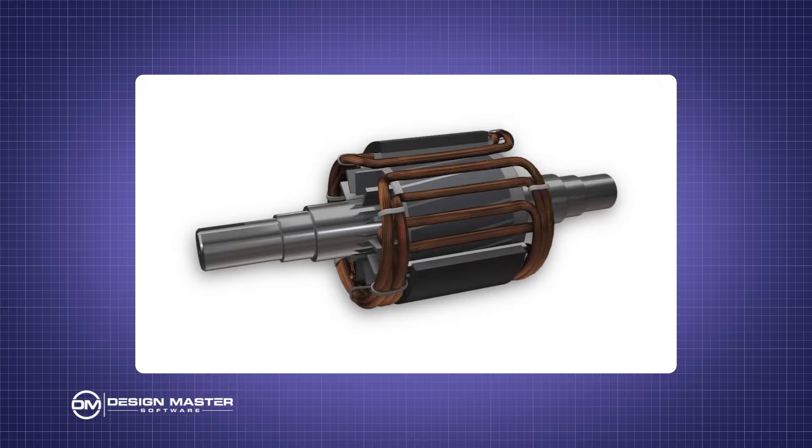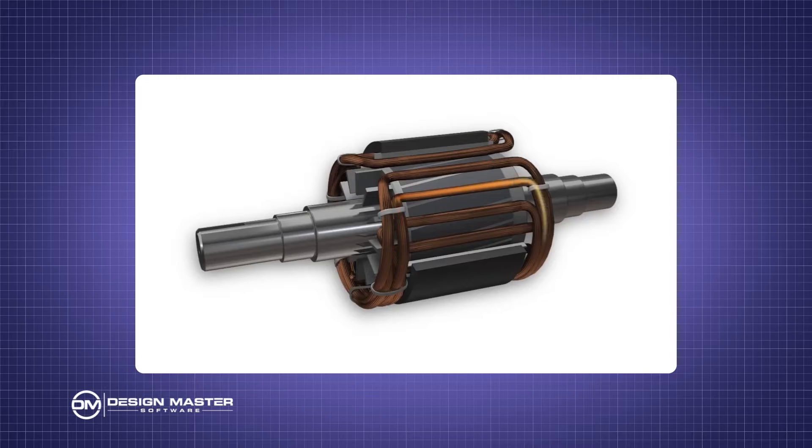The NEC table calls it locked rotor rather than inrush — what's the difference? It's really semantics. The rotor is not literally locked, but the electrons don't know the difference. They rush in and see the rotor is not moving. They don't know if it's locked or just not moving — it looks the same to them. So it's called locked rotor, but it's also inrush, and it's only happening when the rotor is not moving.